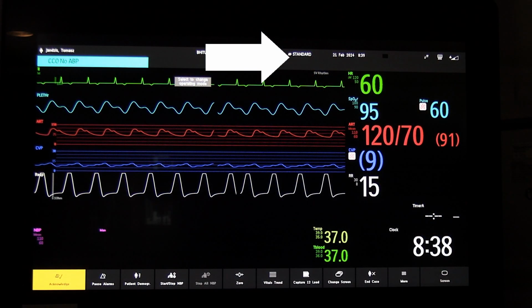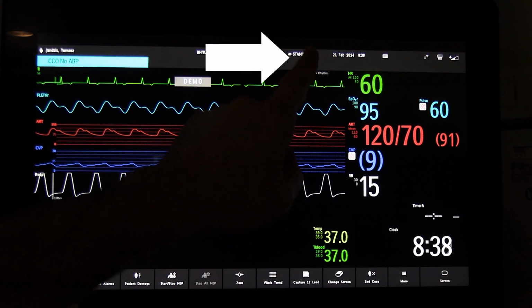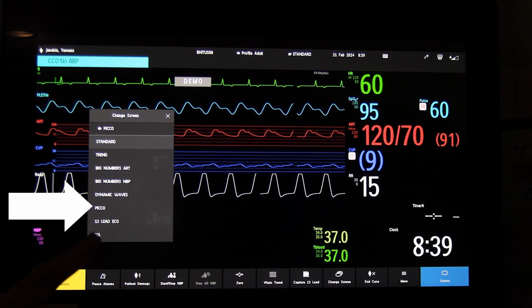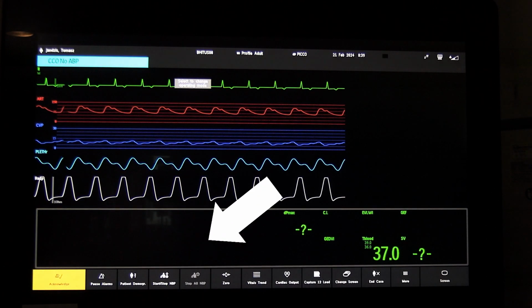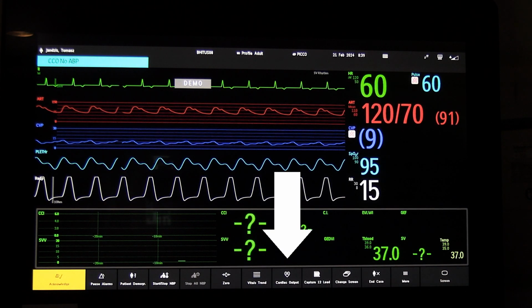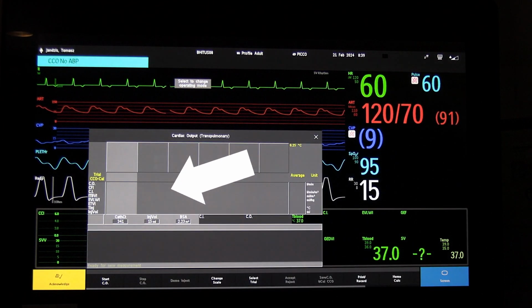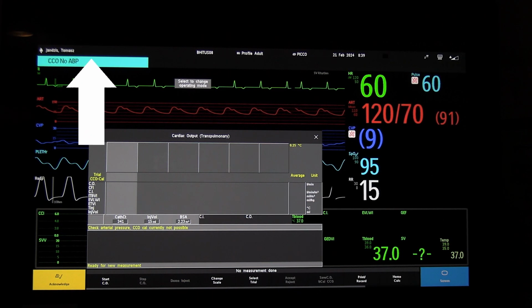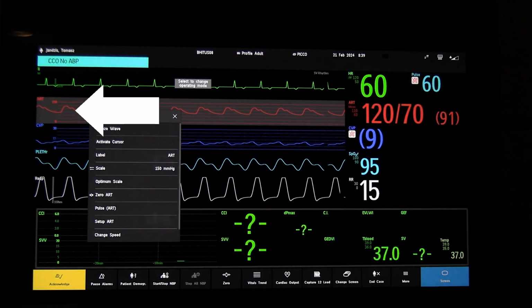Let's return to the monitor. To activate the thermodilution screen, select the word Standard at the top of the screen. This will display the available screen modes, from which you should choose PiCCO. Now touch the newly appeared cardiac output button at the bottom of the screen. Take note of the alarm section, where you may see CCO no ABP. This alarm appears because PiCCO data must come from ABP, not the usual ART label. If the label did not change automatically, please adjust it manually.